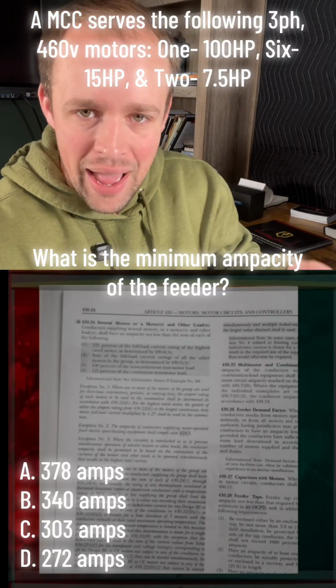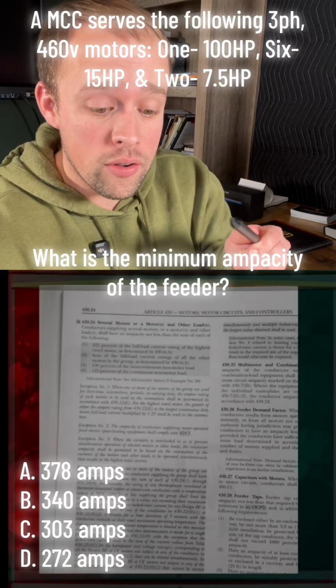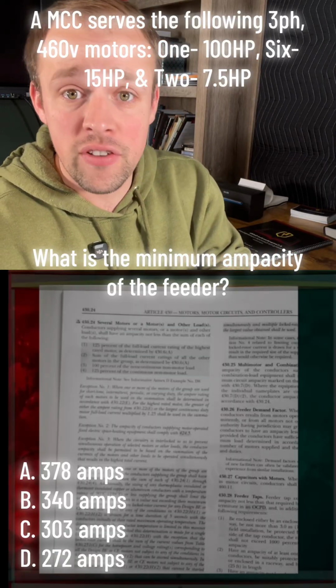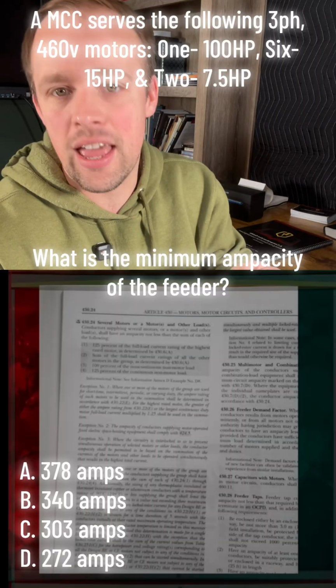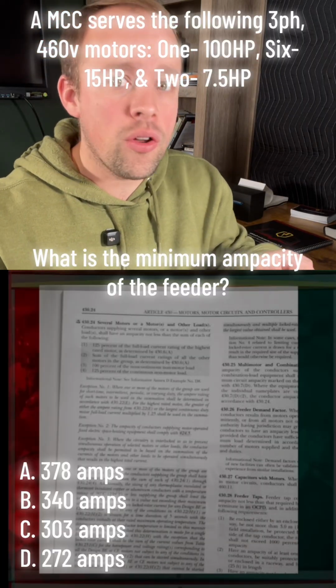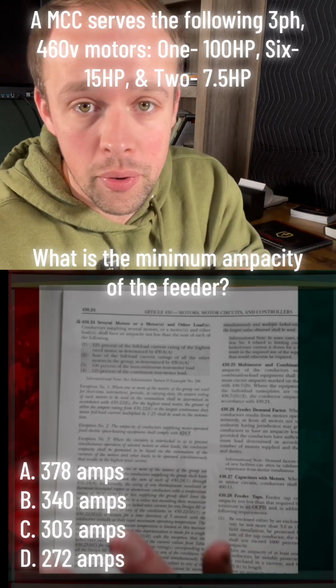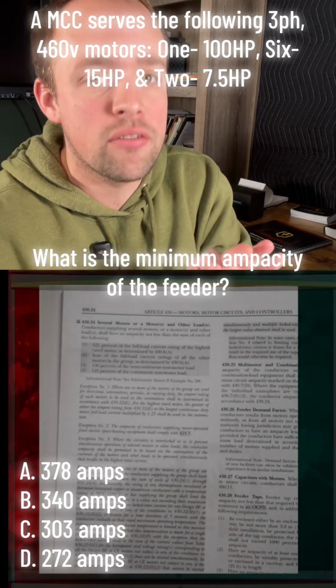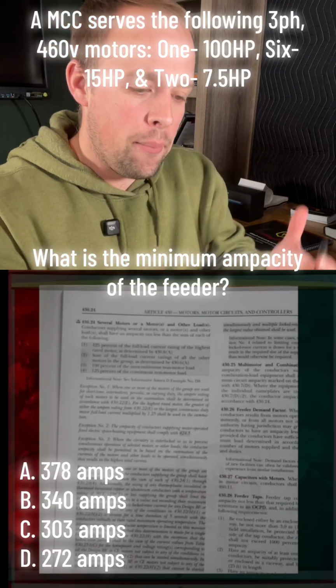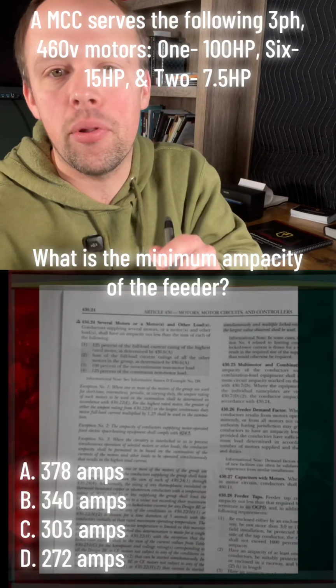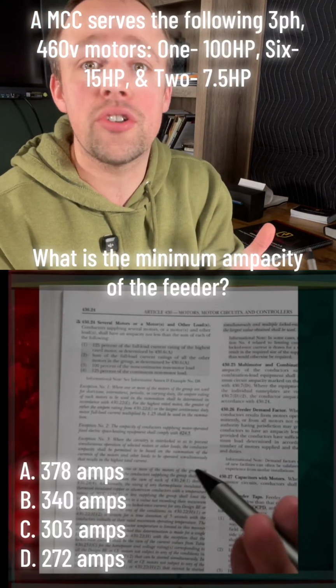It gives us ampacities. So again, for conductors, branch circuit, and feeder short circuit ground fault protection, we use that ampacity. 430.6(A) also says that for motor overload protection and very specific types of motors, we will use the ampacity written on the nameplate of the motor. It's very important to understand that distinction.